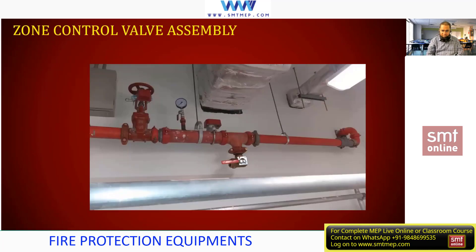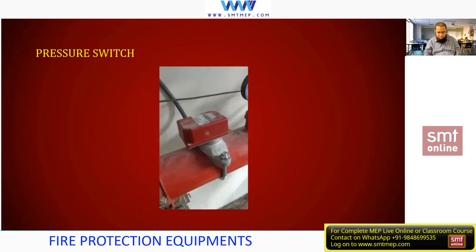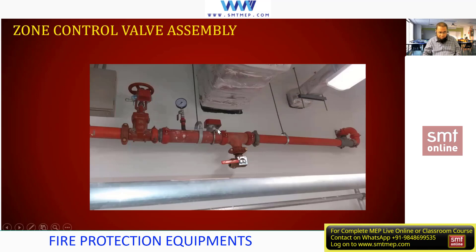Next, you see a preview of the zone control valve assembly. All these accessories together we can call zone control valve assembly. On every floor you'll find this zone control valve assembly. If the number of sprinklers is less than 280, one assembly is needed; if more than 280, an additional zone control valve is required. In this zone control valve assembly, you have the OS&Y gate valve with supervisory switch, a pressure gauge, a pressure switch, and a test and drain valve.